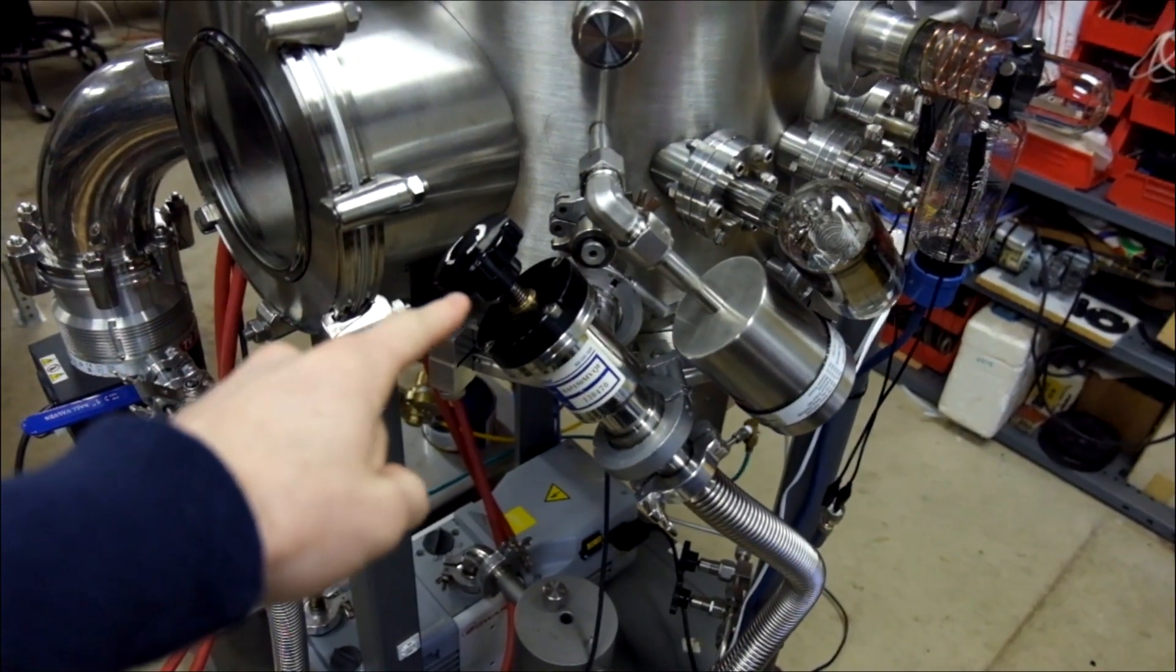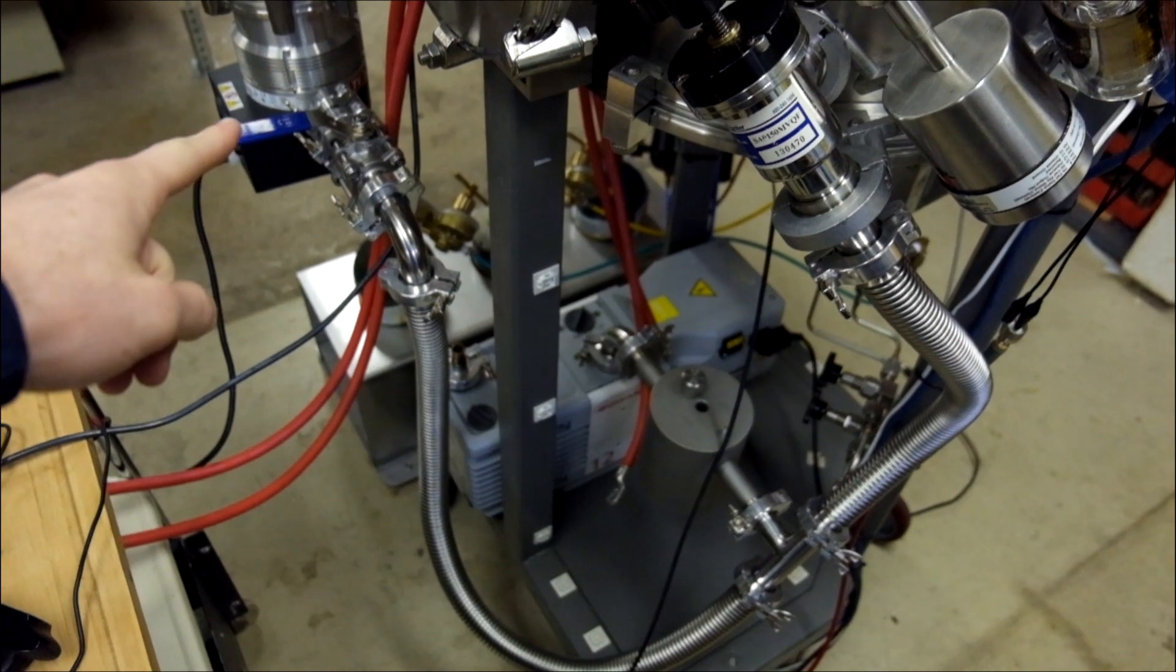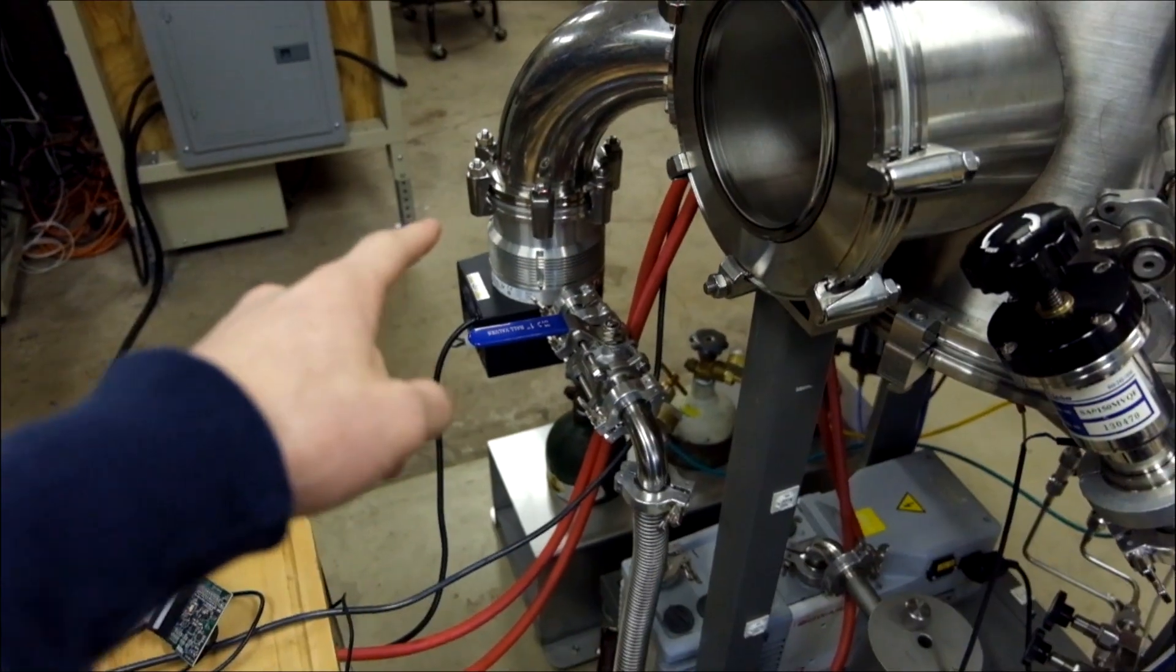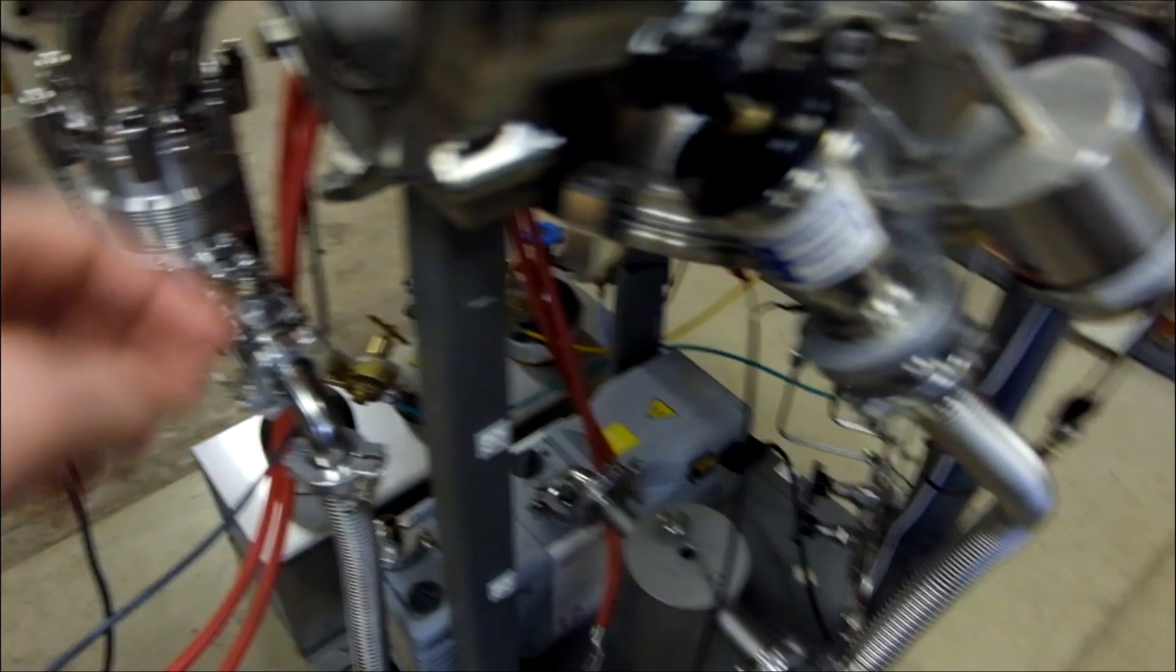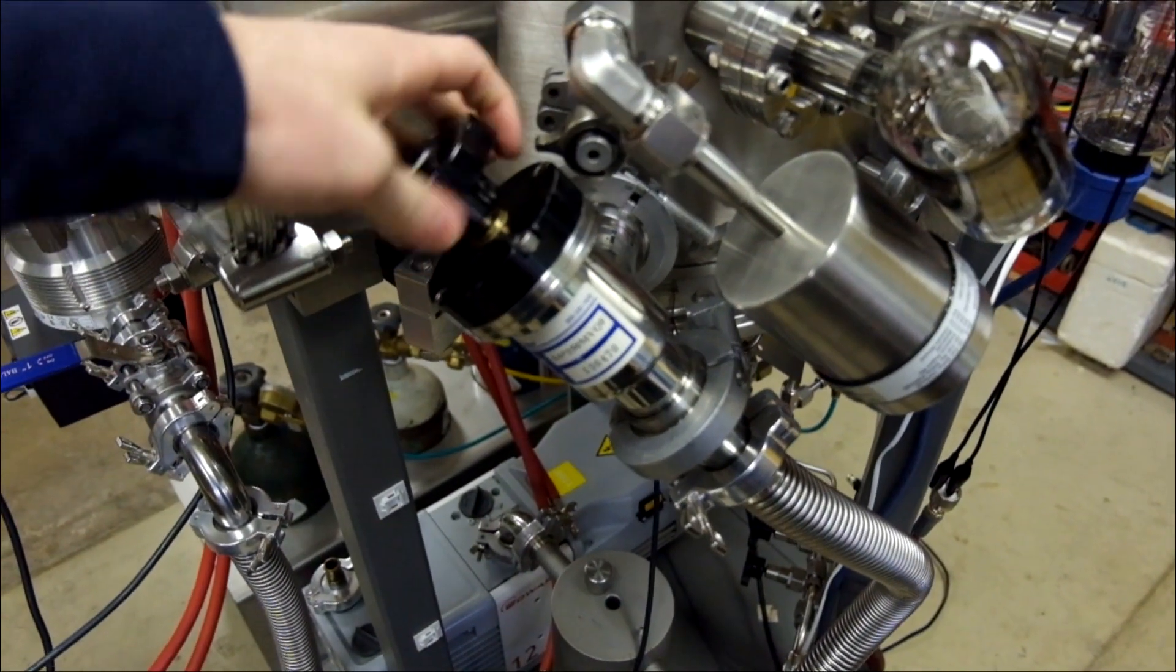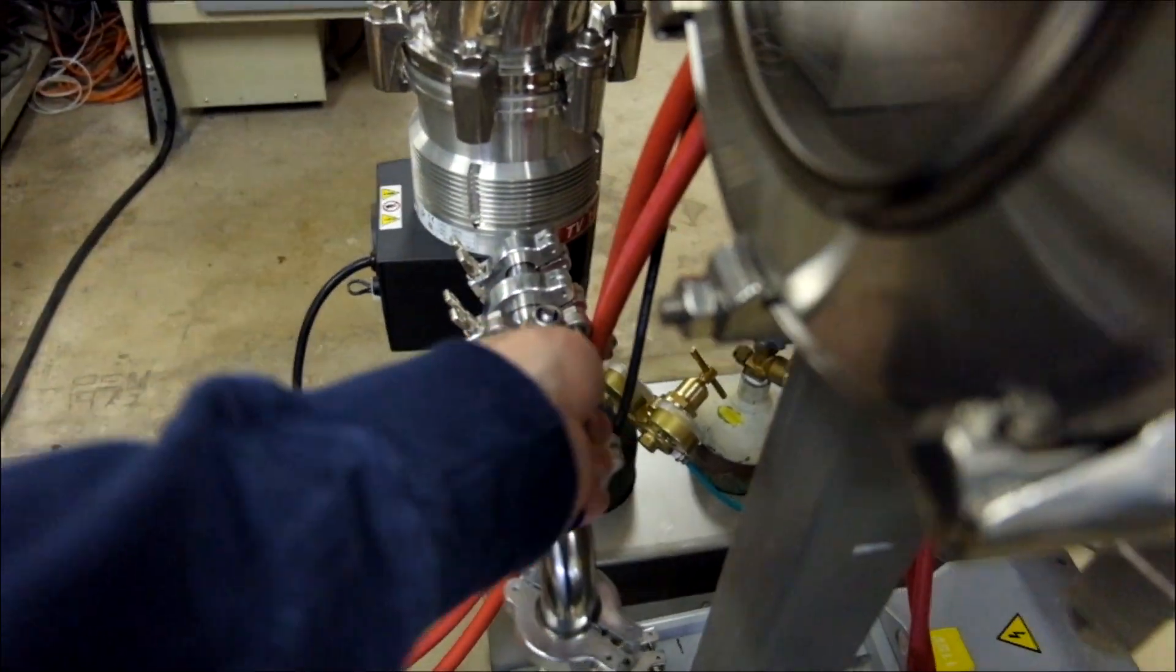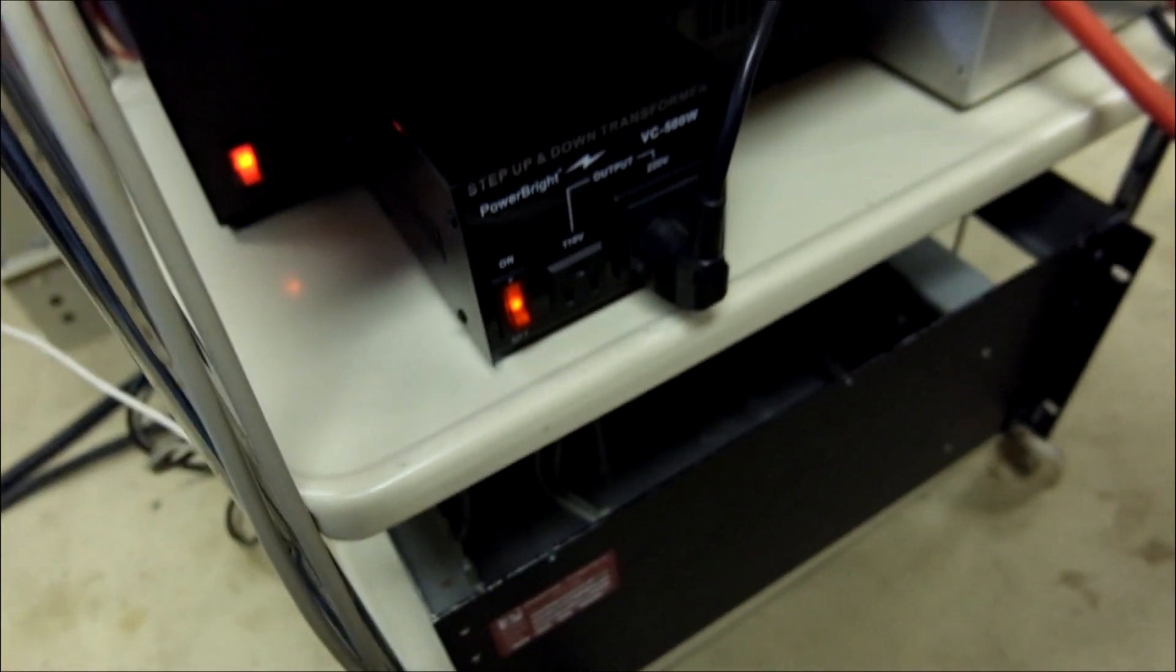So now, to turn the turbo pump on, I'm going to close the isolation valve to the chamber, and then I'm going to open up that ball valve with the blue handle there, and you can see the roughing line is pretty simple. Then that's going to switch to the mechanical pump, instead of pumping the chamber, it's going to be backing the turbo pump, and then I'm going to flip on the step-up transformer down here. We're just going to send 240 volts to the turbo pump. So we'll close this guy, open the blue handle, and then flip on the step-up transformer.